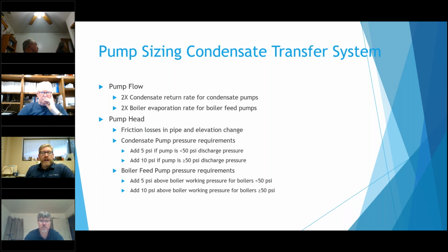Boiler feed, it's a little bit different because you're going into a boiler, and that boiler could be 100 pounds or 75 or 10. So you got to make sure that you're overcoming that. So you want to be at least 5 pounds above the boiler working pressure if it's 50 pounds, or 10 pounds if it's above 50. Otherwise, the water just won't go in there. So you got to worry about your friction loss as well as your boiler pressure for boiler feed units.